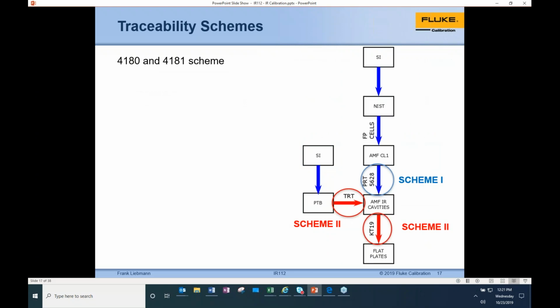I went through this a little bit, where the SI comes from NIST or your national lab, usually in the form of fixed point cells. And when we talked way back at the beginning, IR is good, but it's not the best way to take a temperature measurement. There are other techniques, usually contact calibration, because we can go right to our fixed point cells, which provide the lowest uncertainty. Everybody's agreed, for example, on what the triple point of water is and how to achieve it, things like that.